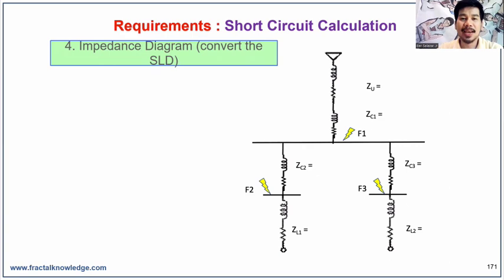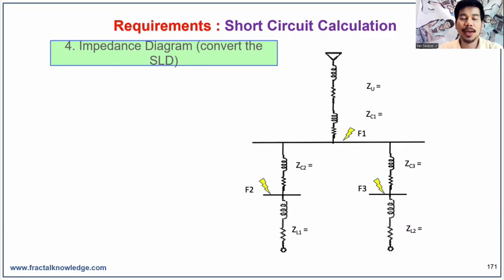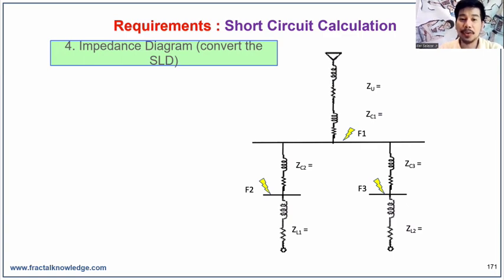The fourth requirement is to simplify the single line diagram to an equivalent impedance diagram. You need to eliminate all non-contributors to short circuit and convert all electrical components to impedances. The impedance diagram should be labeled carefully; buses should be properly identified for the number of fault points and the termination for the kAIC rating of protection.